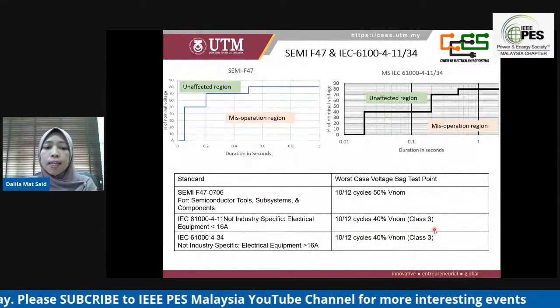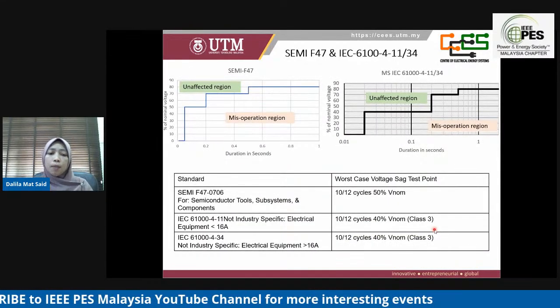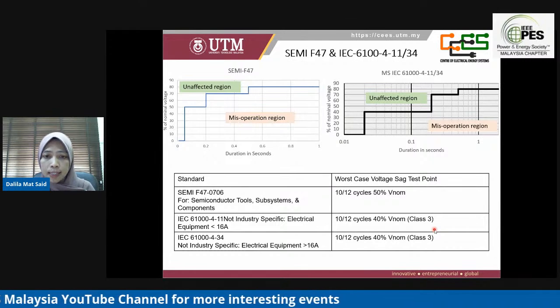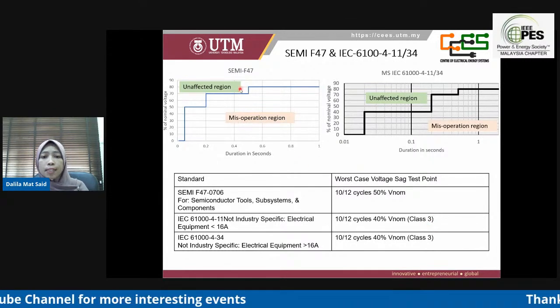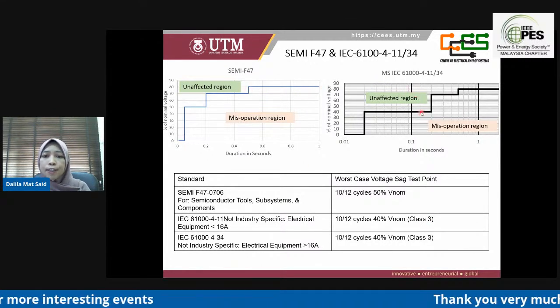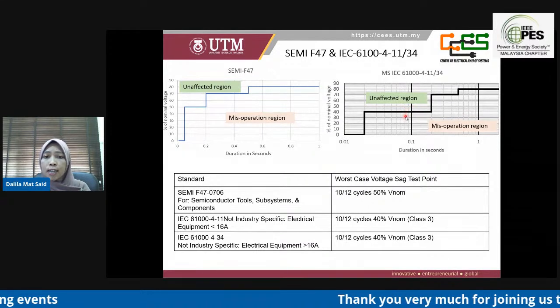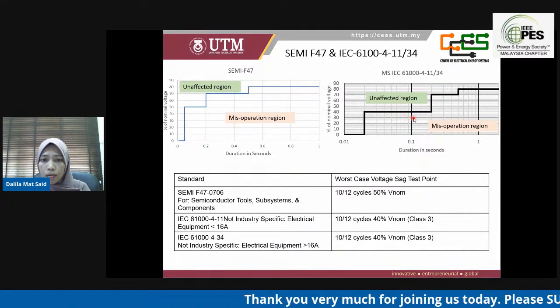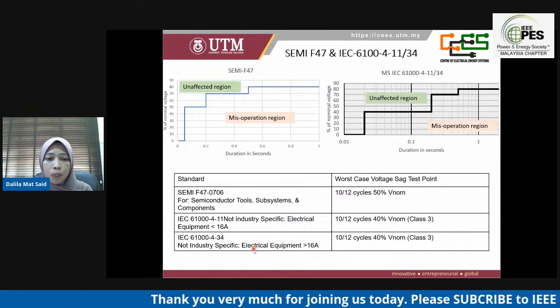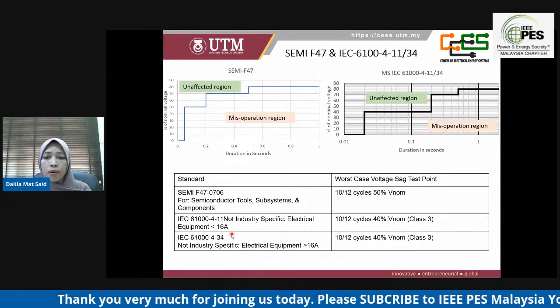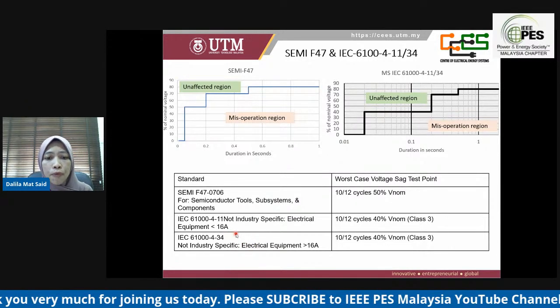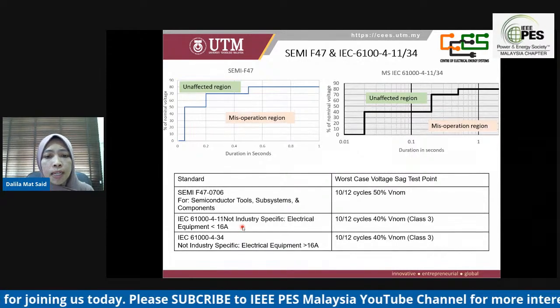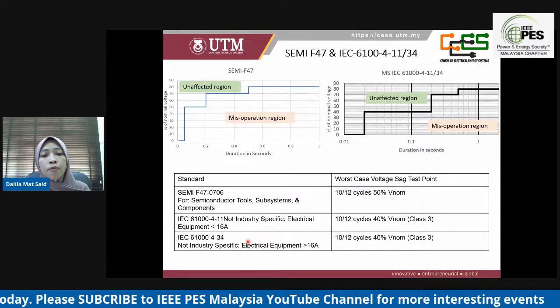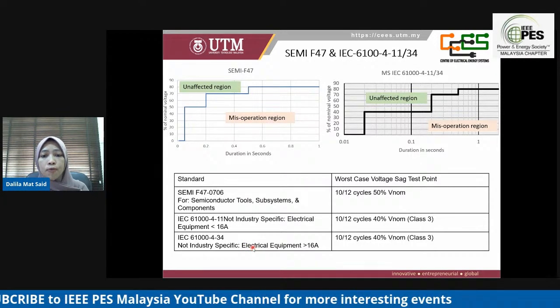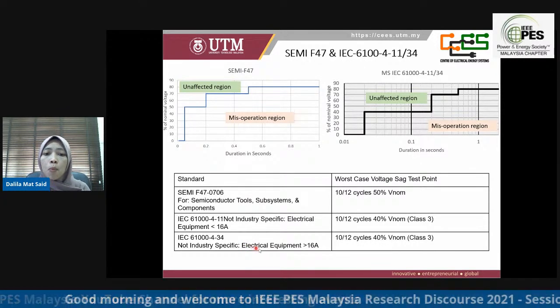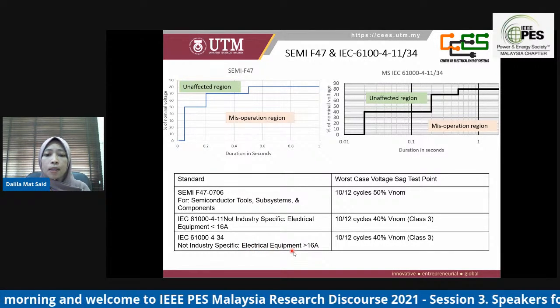Another standard related to the immunity level of voltage sag is SEMI F47 and IEC 61000-4-11 and 4-34. So we can see the difference between these two standards. 4-11 is for electrical equipment with current less than 16 A, and 4-34 is for electrical equipment with current more than 16 A.